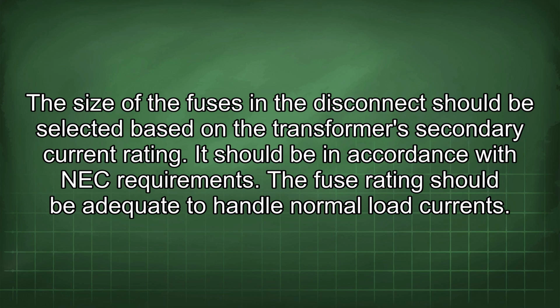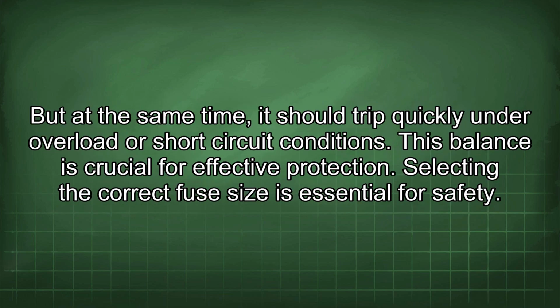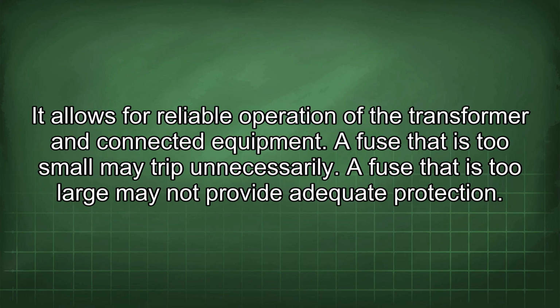The fuse rating should be adequate to handle normal load currents, but at the same time it should trip quickly under overload or short circuit conditions. This balance is crucial for effective protection. Selecting the correct fuse size is essential for safety. It allows for reliable operation of the transformer and connected equipment.